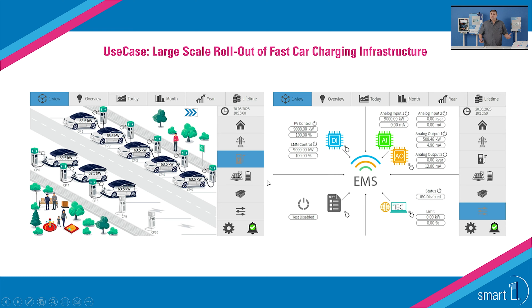So what does the system actually do? At the end of the day, it reads data from this meter in real time. Through Ethernet, it polls this meter very fast in real time, and based on the information from the meter, it does automatic limitation of each individual charging point, controlling actively the power of each charging point individually.